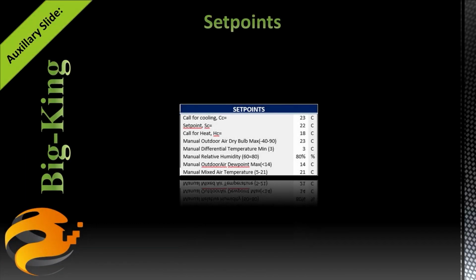In the setpoint section, the setpoint, SC, is the desired indoor air temperature, while call for cooling, CC, is the temperature at which the thermostat will call for cooling, and HC is the call for heat setpoint. These are separate to facilitate the different styles of control logic for the various equipment. This deadband can also be modified separately for equipment on a manufacturer-by-manufacturer basis based on their individual styles of control logic.